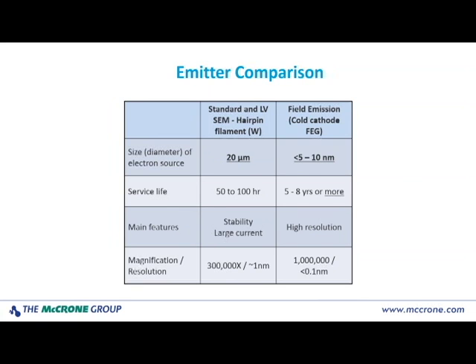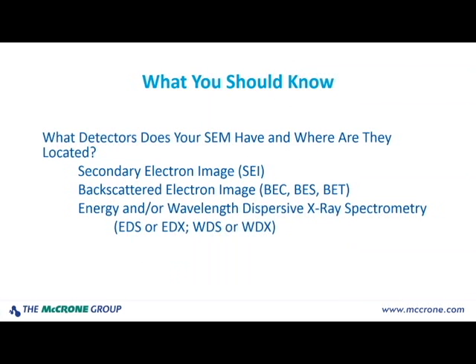If you go to the field emission, they have the capability of going to a million x. This takes a lot of effort to get to. You have to have a room that is well protected with no electromagnetic emissions anywhere near the instrument; otherwise, it will distort your image. But you can achieve resolutions of less than a tenth of a nanometer — down into the angstrom range.